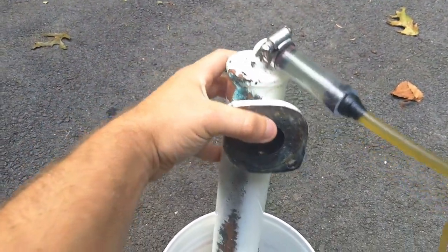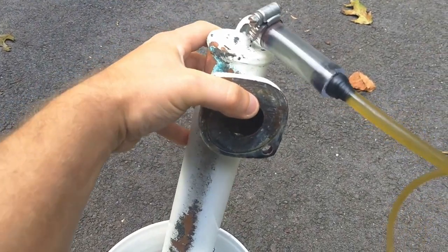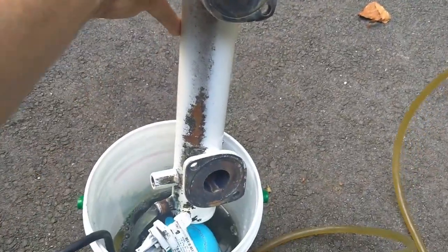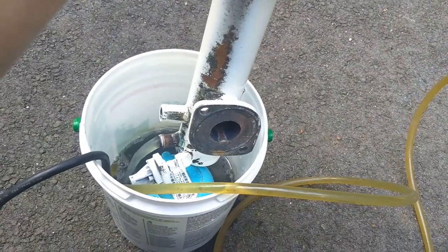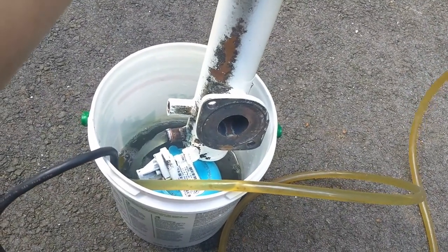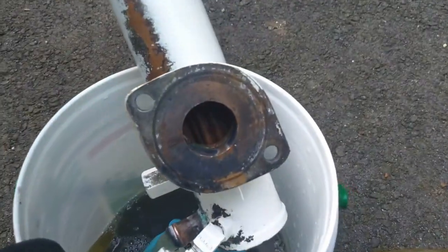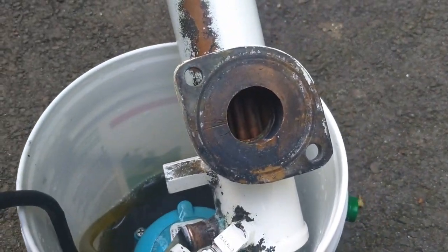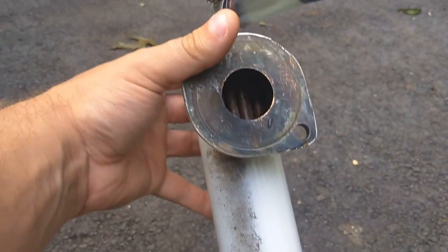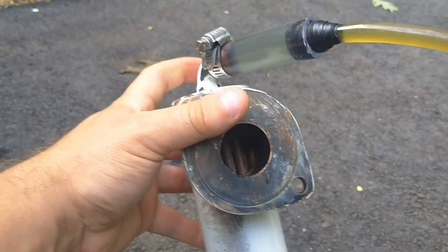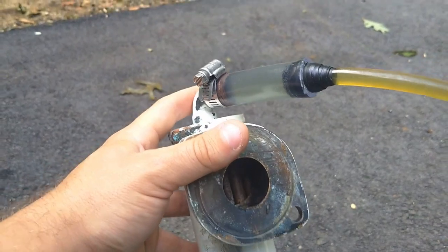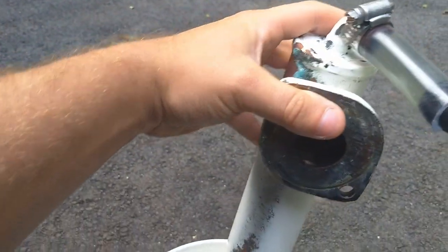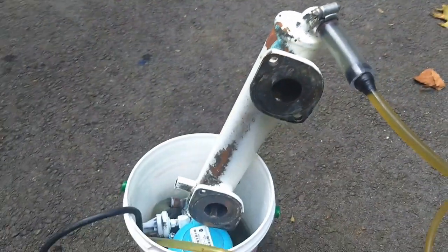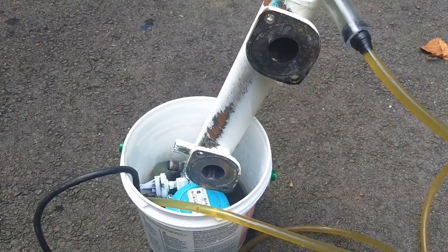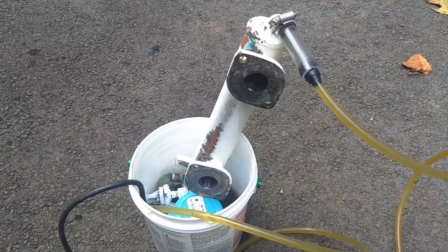Normally the intake is down at the bottom here near the pressure switch or sensor, and it goes through these copper pipes on the inside. That's where the raw water normally comes up through, and then it exits up here at the top. So I'm basically back flushing this using this small pump, circulating the barnacle buster through it backwards.